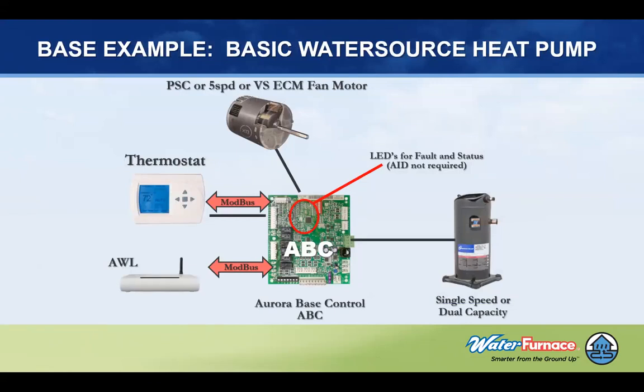So I want to go now to what are the basics inside a system and what allows us to have a remote diagnostics and troubleshooting process. If we look at the base control system that is in most heat pumps in the industry, you have a control board that controls a single speed or a dual capacity compressor. You have LEDs that allow you to know what's the status of the piece of equipment at a given time. You can control any type of fan motor.